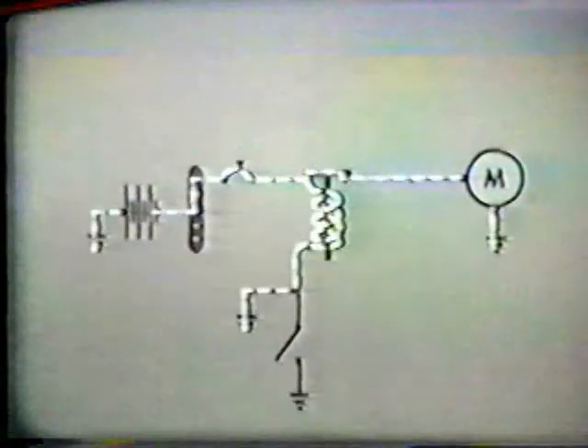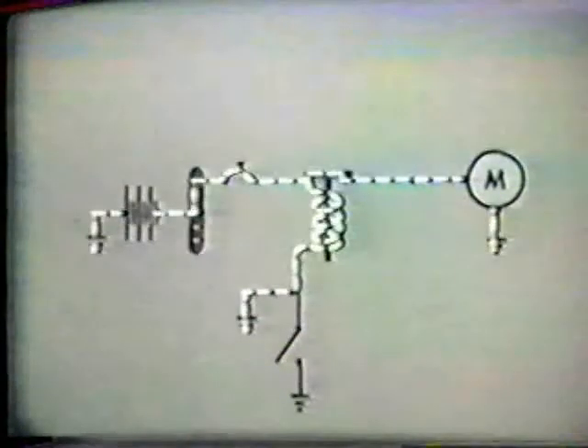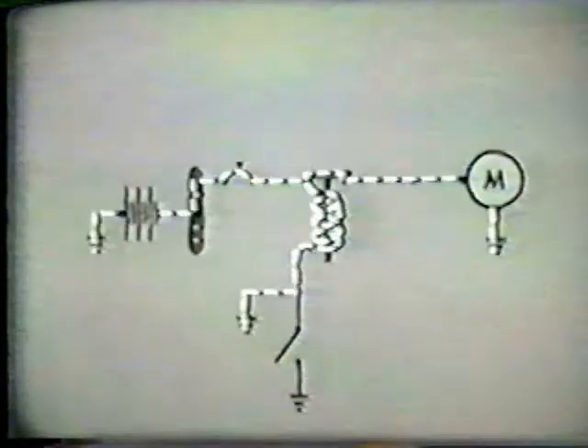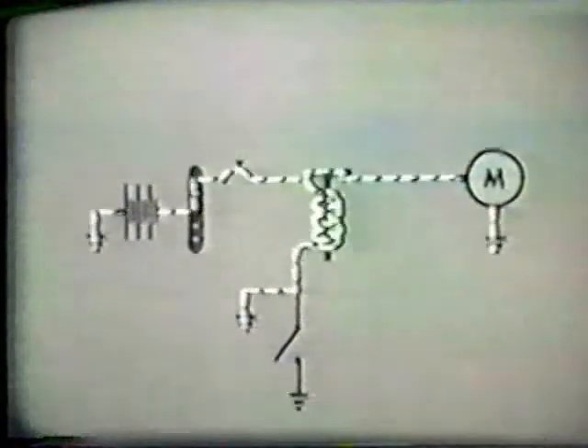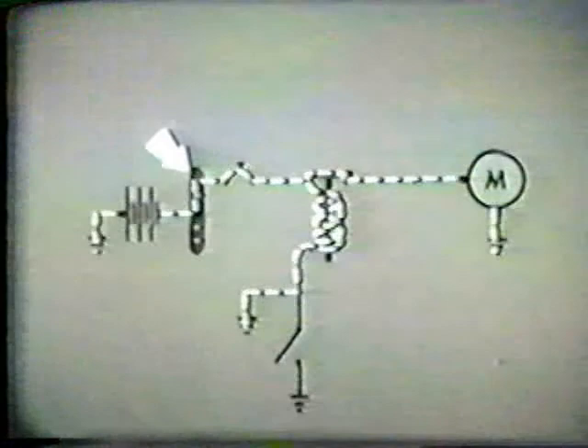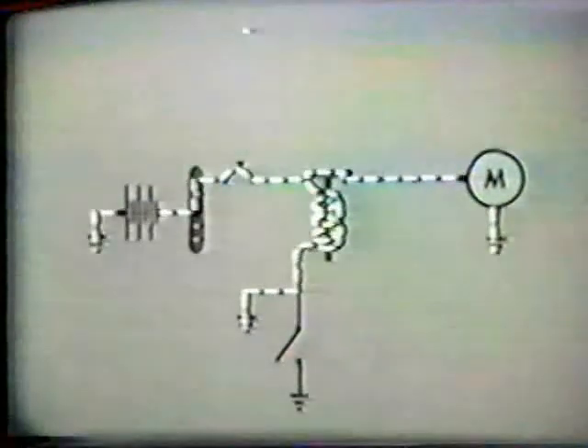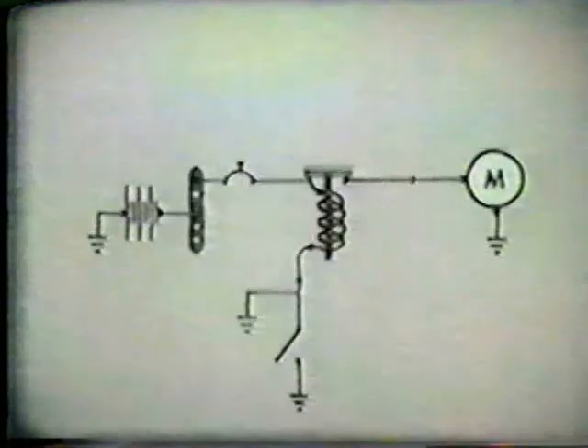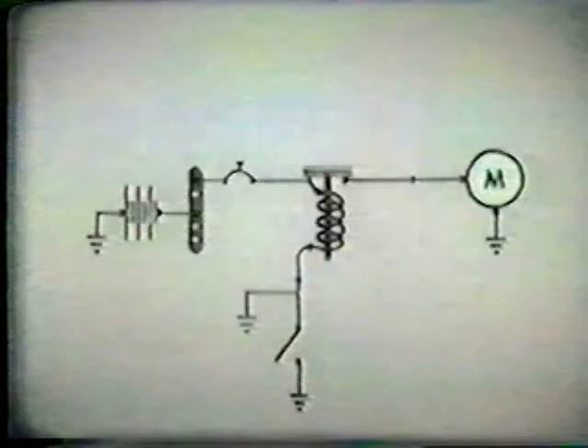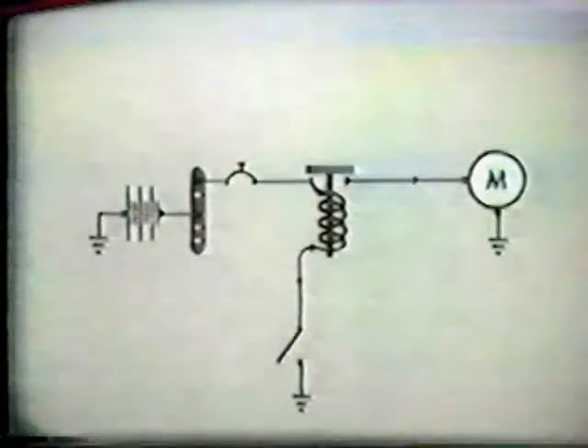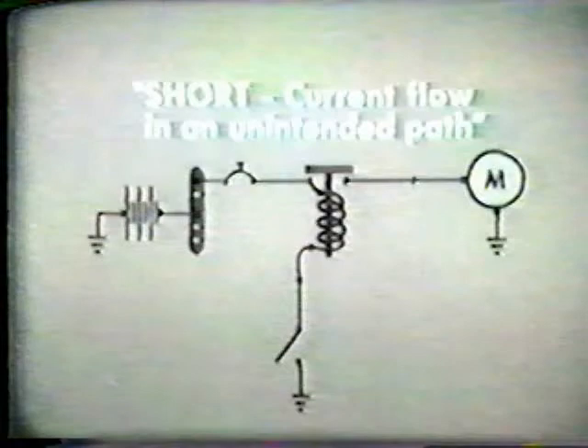Sticking contacts must be dealt with quickly by disconnecting the power supply at any convenient point, by pulling a circuit breaker or disconnecting a wire. Allowing some relay-controlled units to run too long may damage them severely. Remember, the definition of a short is current flow in an unintended path.